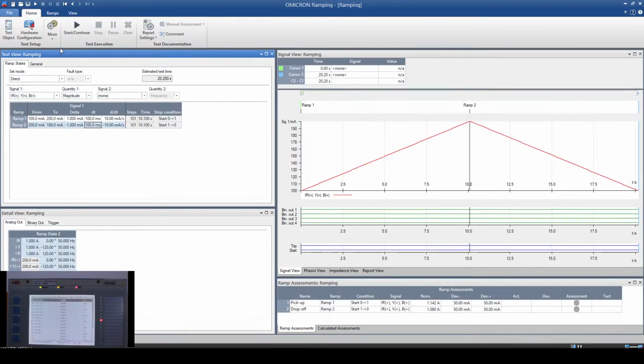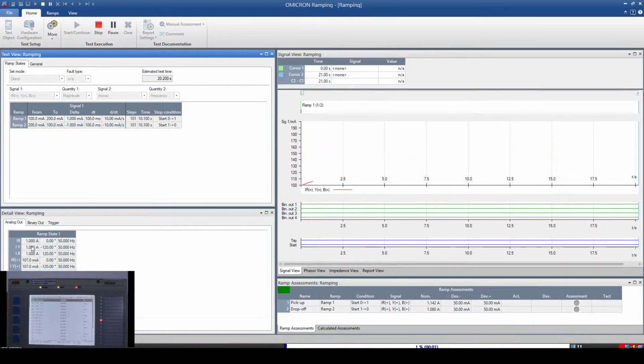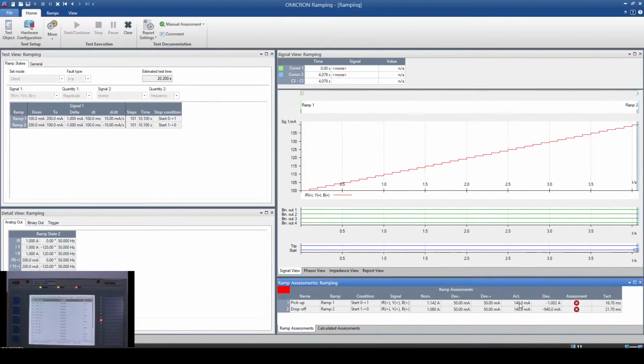So now what we can see over here is, just press start, all the 3 phases. It is just an addition, right? How much on top of your original signal we have actually performed. So here you can see that we have not changed the assessment. So 1 plus 0.140, that is 1.140, would be your actual pickup value, right?